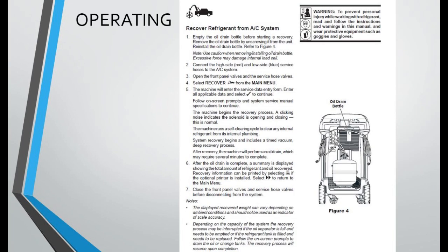Operation: Recover refrigerant from AC system. 1. Empty the oil drain bottle before starting a recovery. Remove the oil drain bottle by unscrewing it from the unit. Reinstall the oil drain bottle. Refer to Figure 4. Note, use caution when removing and installing the oil drain bottle. Excessive force may damage the internal load cell.